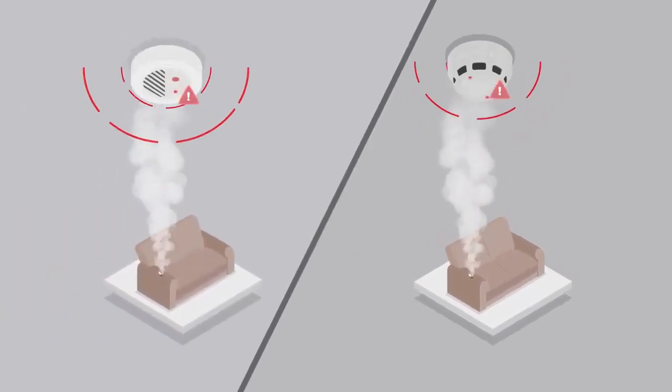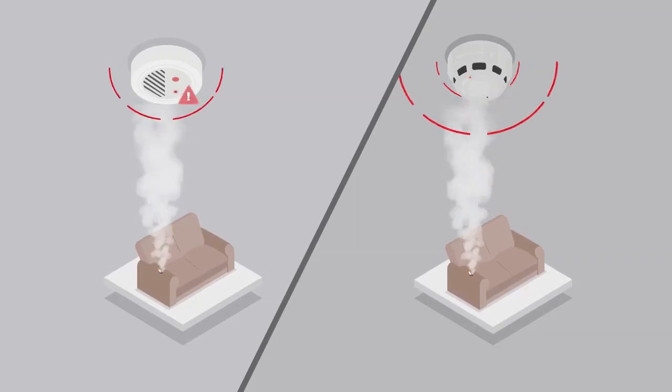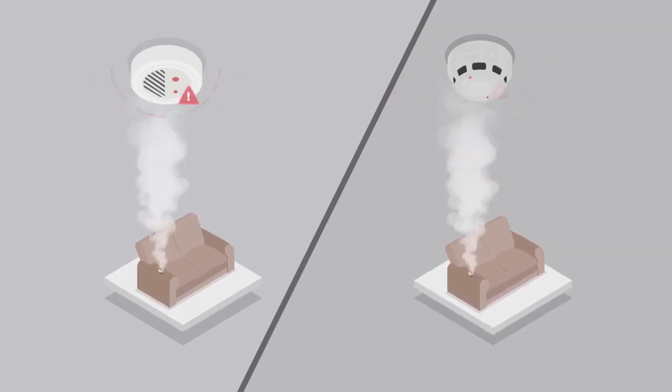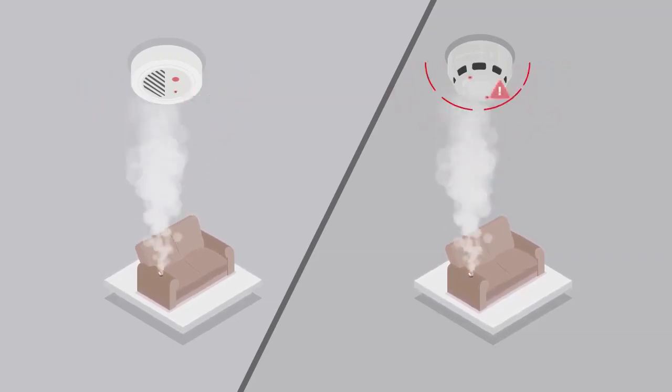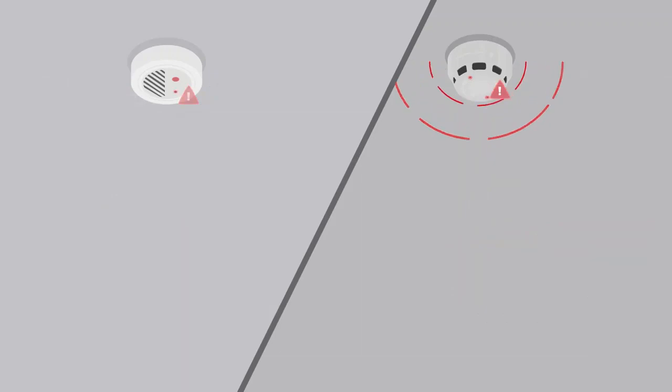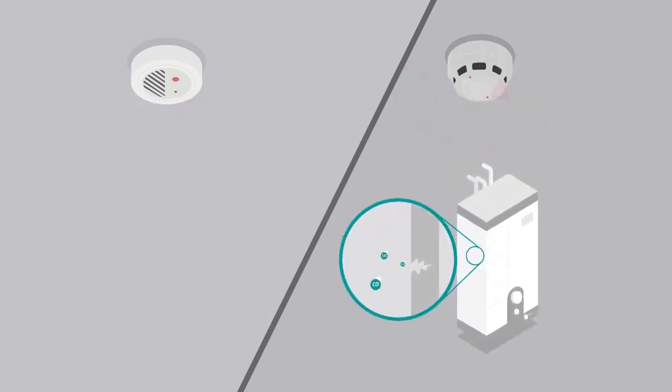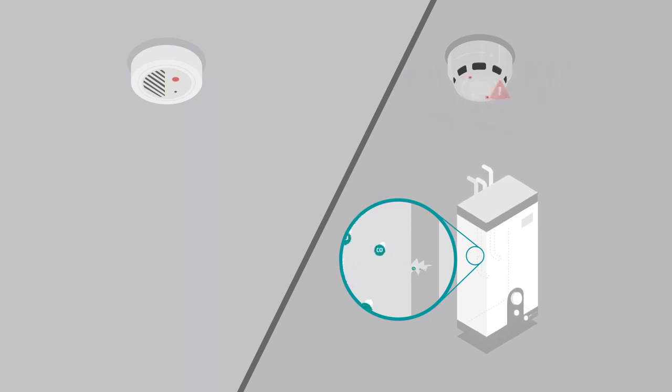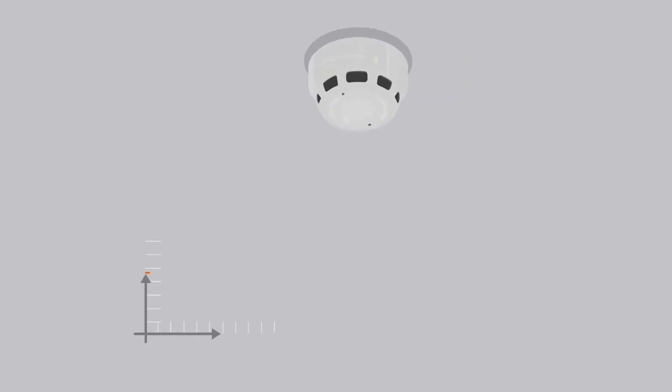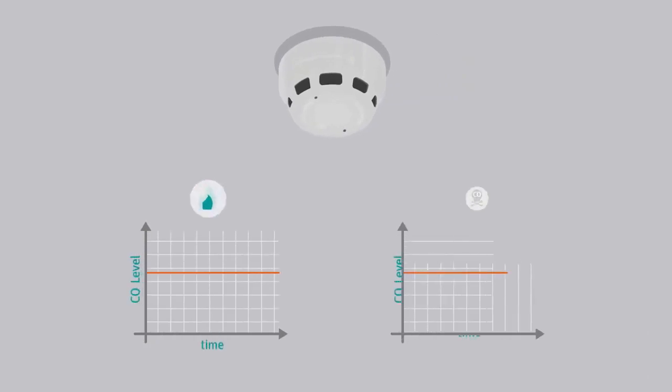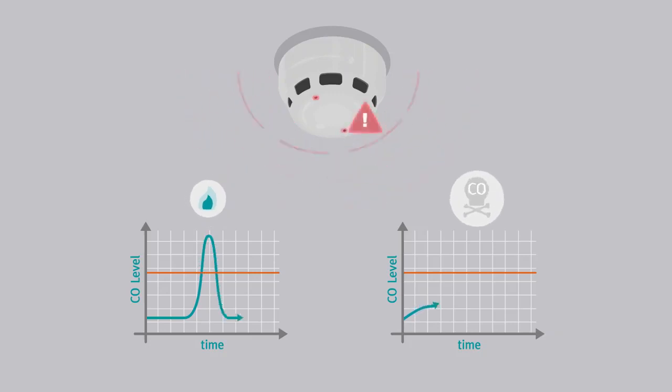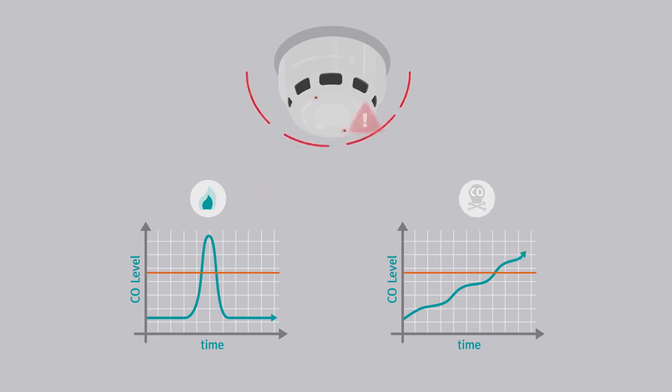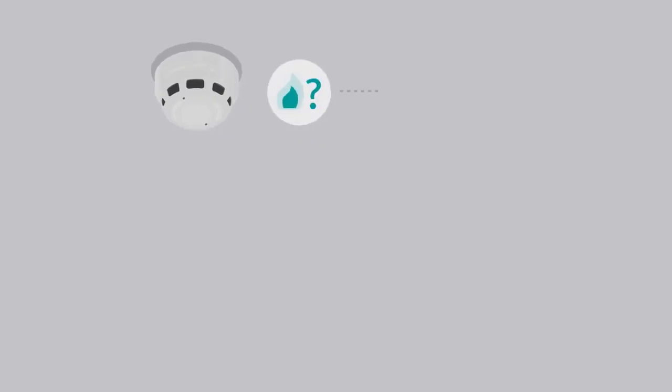Traditionally, CO detection is integrated into a multisensor to assist with the rapid detection of smoldering fires through the release of CO gas. However, the ACD can also recognize the threat of carboxyhemoglobin toxic poisoning, commonly referred to as carbon monoxide poisoning. Carbon monoxide poisoning can be suffered as the result of either a sudden high exposure to CO or a prolonged exposure to lesser amounts of CO over time. The ACD therefore monitors for both criteria and will report an alarm condition if either scenario is met.